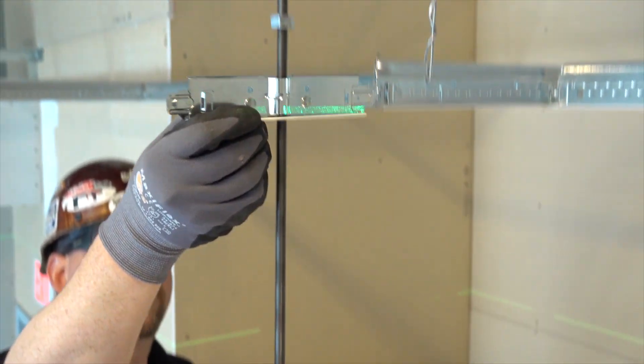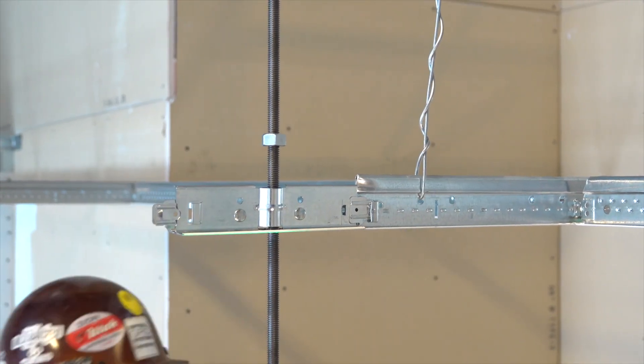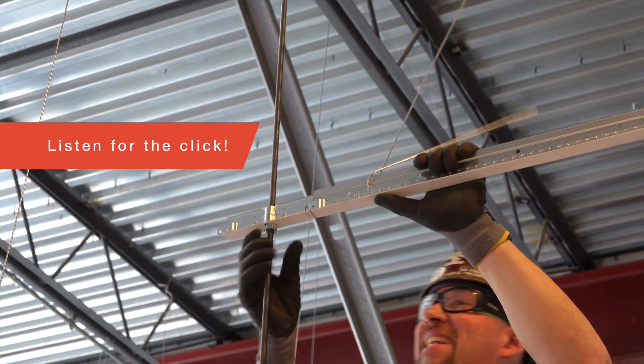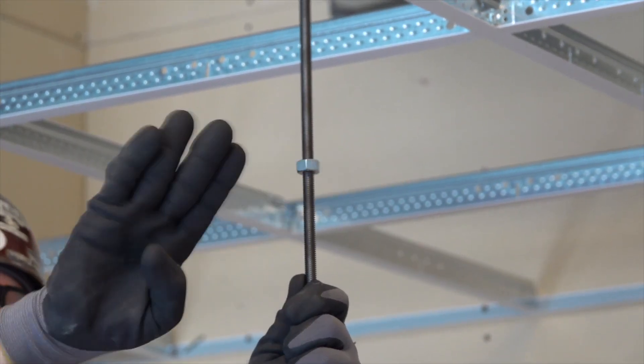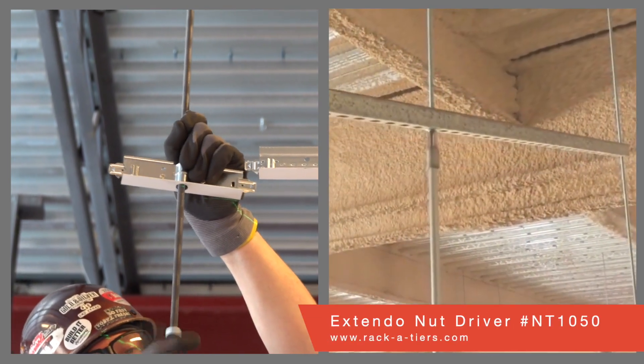The CLP stabs into new 7 foot 6 or 9 foot 6 main beams for typical 8 or 10 foot data center pods. Speed up the threading of nuts on long threaded rods with an extender like the Extendo Nut Driver.